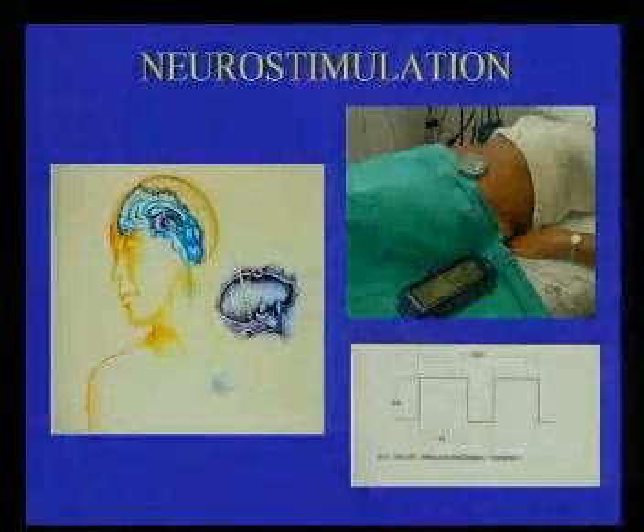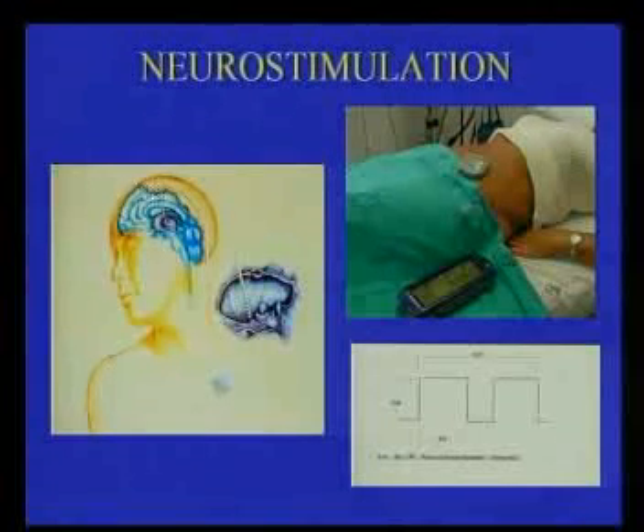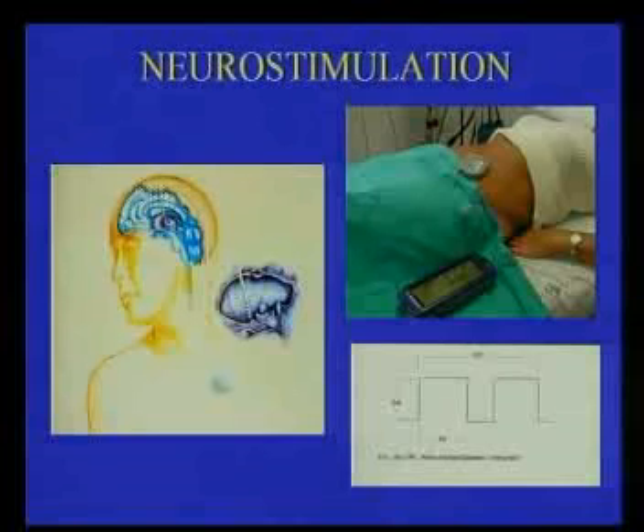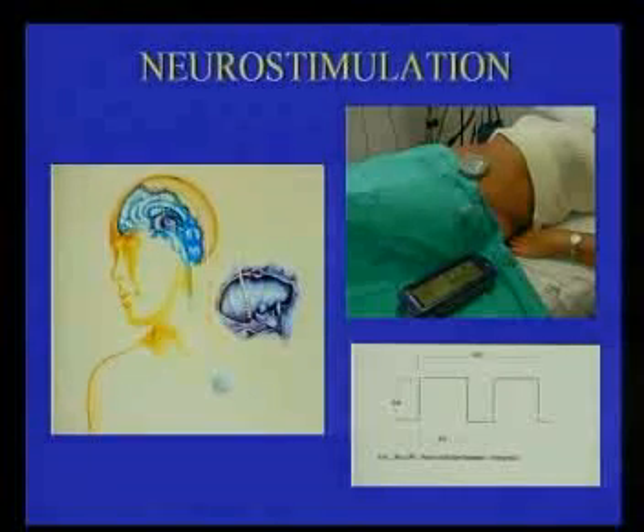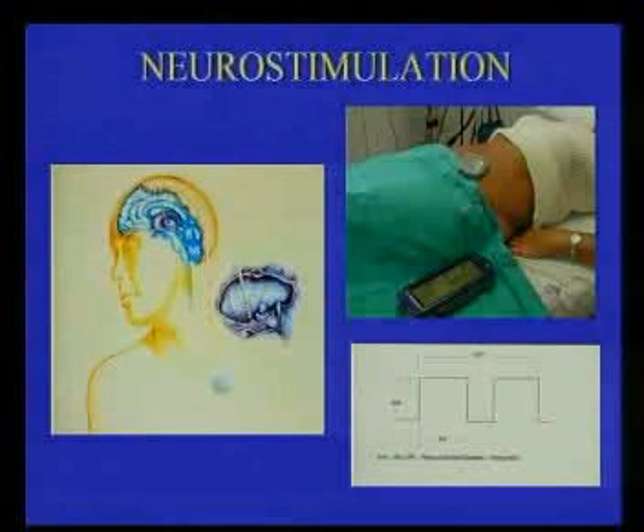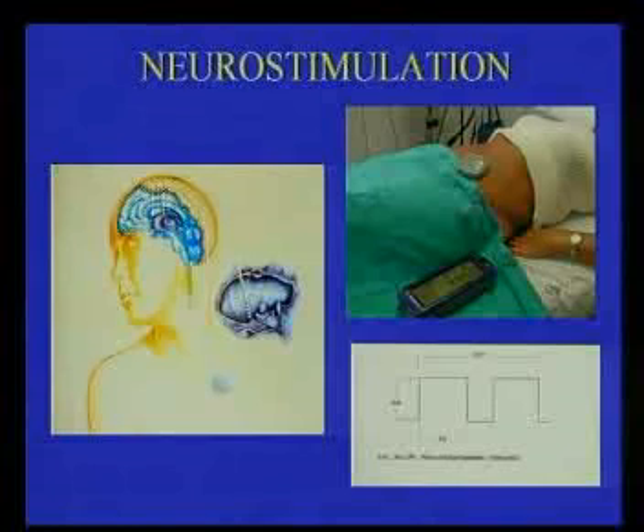On the other hand, if we focus on a more sophisticated system of neurostimulation implanted in the brain, here we find the same thing. Basically, we have an electrode which delivers an electrical impulse on the brain and a generator which is fully implanted. The patient has no peripherals or devices outside, and there is a cable towards the generator. The calculations are the same. However, here, since we have more electrode contacts, you may choose 1, 2, 3, 4 contacts, bipolar, cyclic. You can play a little bit. The stimulation parameters of the implanted generator can be changed by means of an external device and then transmitted on the basis of radio frequency.